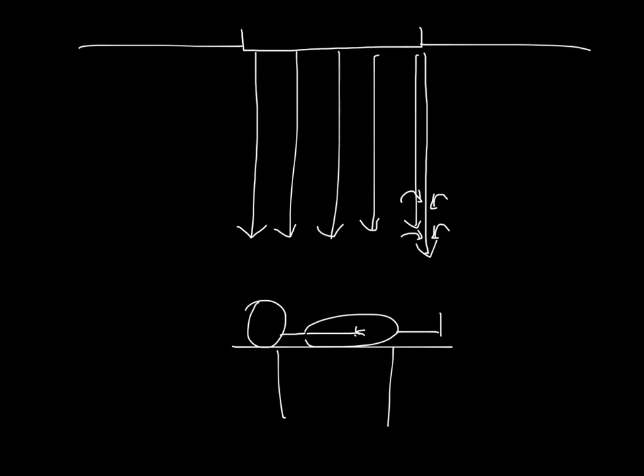So it's not technically laminar flow. Think of each perforation as a column of air, and as the air moves downward it'll induce some air from around the column into the column. What we often refer to as laminar flow diffusers are really unidirectional flow non-aspirating diffusers.